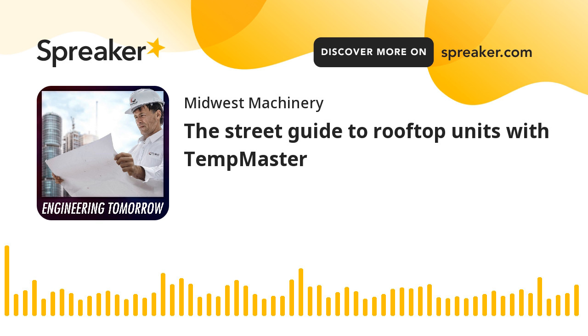Now, before any of that would happen, before you'd have to have a guy on a roof, you'd get a fault because we have those sensors integral to the unit. The unit would get a fault and send you a warning before it had a problem, before you have to shut it down and take a compressor out. Now you can go up there and maintenance the unit, maybe charge up the refrigerant, plug up a tiny leak, what have you, without having any downtime. You can do it at a time when the unit was already scheduled to be down. And scheduled maintenance, trust me, if you don't know, is much less of a headache than non-scheduled maintenance. If the unit's down and you've got, whether it's hot people or an office or a surgery suite that can't have a unit being down, this is where the crucial serviceability comes into play.